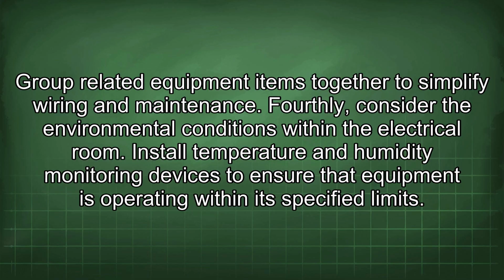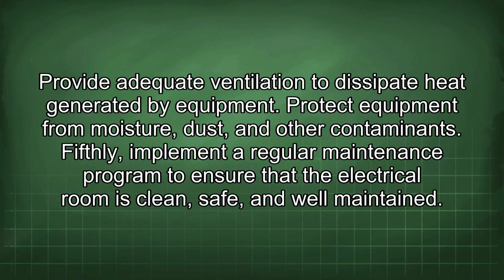Fourthly, consider the environmental conditions within the electrical room. Install temperature and humidity monitoring devices to ensure that equipment is operating within its specified limits. Provide adequate ventilation to dissipate heat generated by equipment. Protect equipment from moisture, dust, and other contaminants.